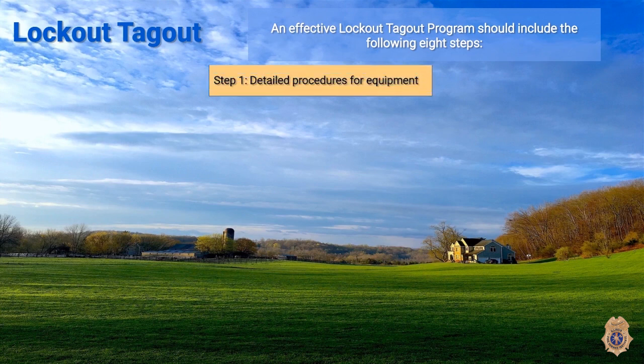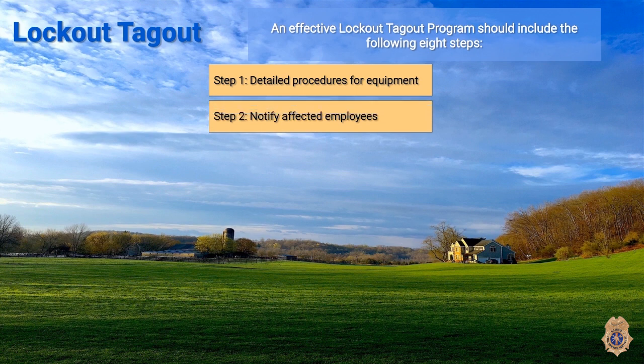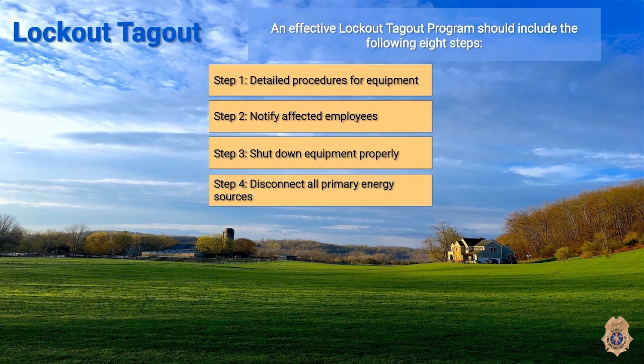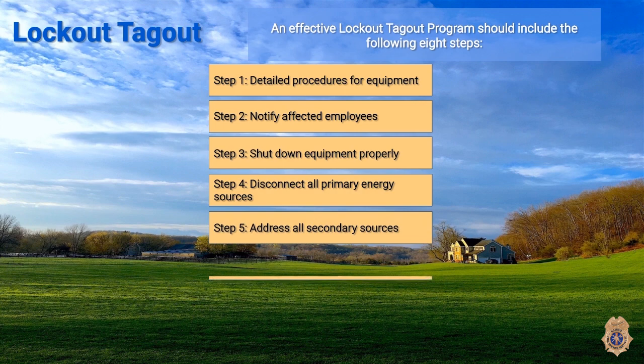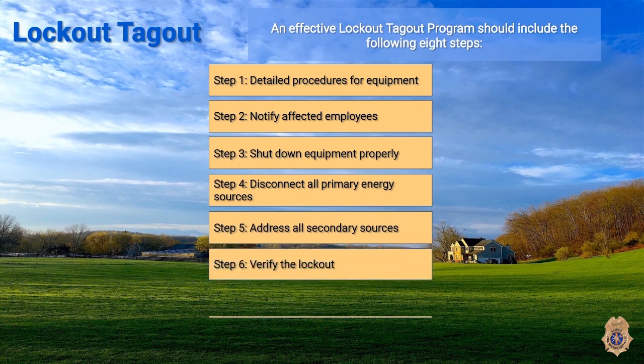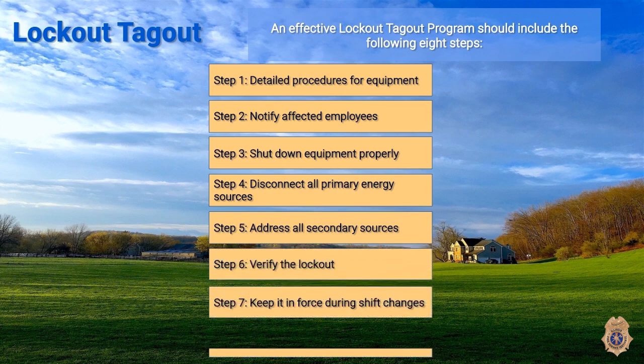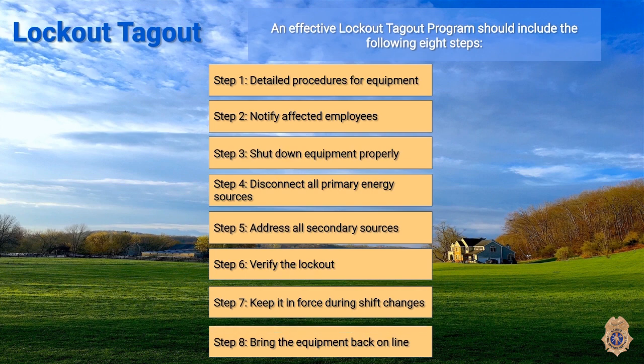Step 1, detailed procedures for equipment. Step 2, notify affected employees. Step 3, shut down equipment properly. Step 4, disconnect all primary energy sources. Step 5, address all secondary sources. Step 6, verify the lockout. Step 7, keep it in force during shift changes. Step 8, bring the equipment back online.